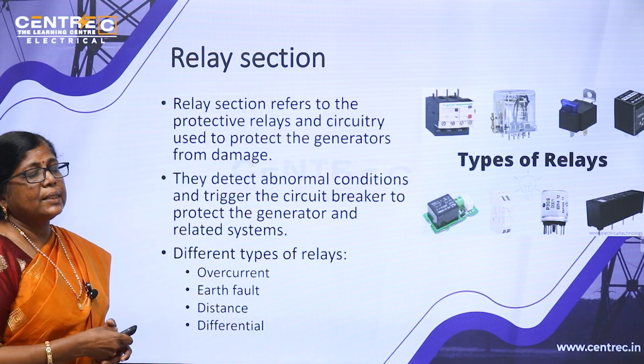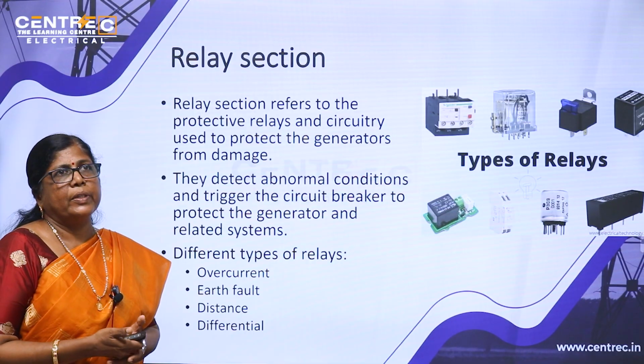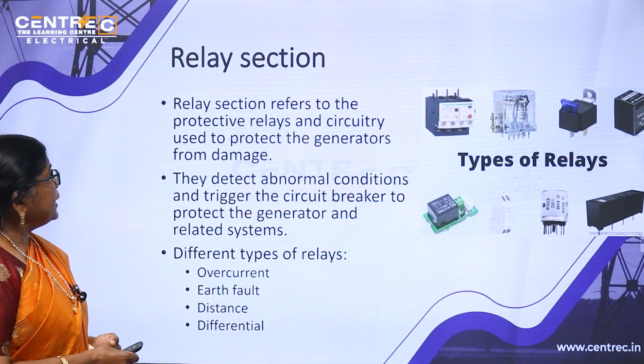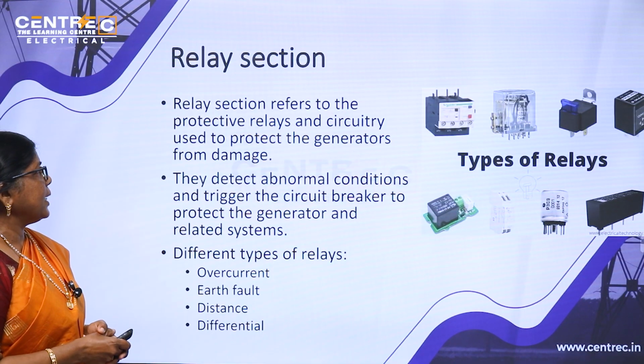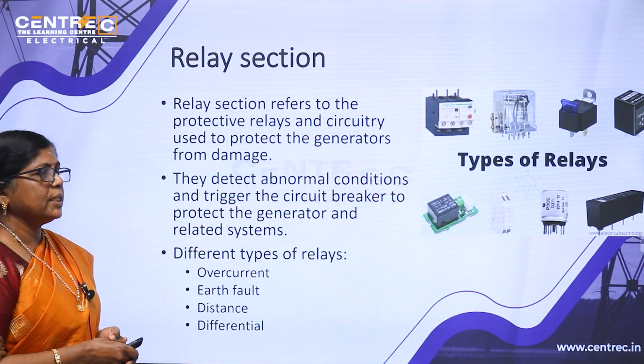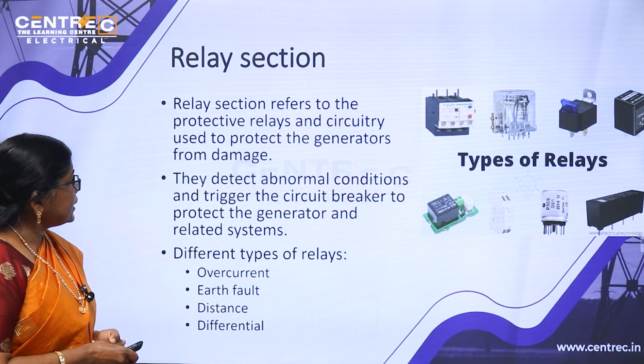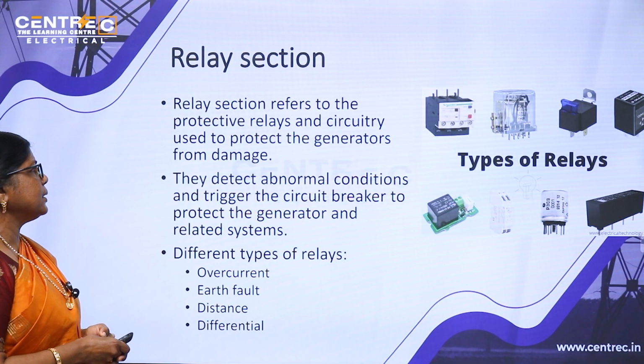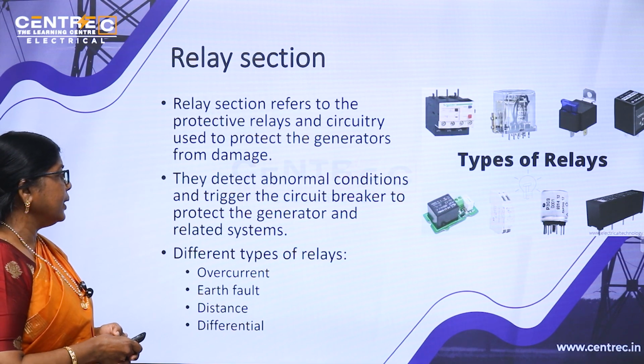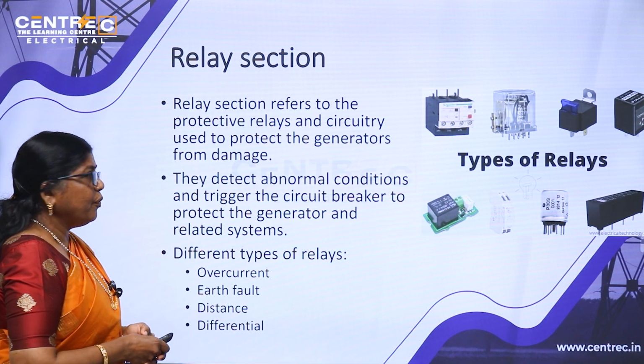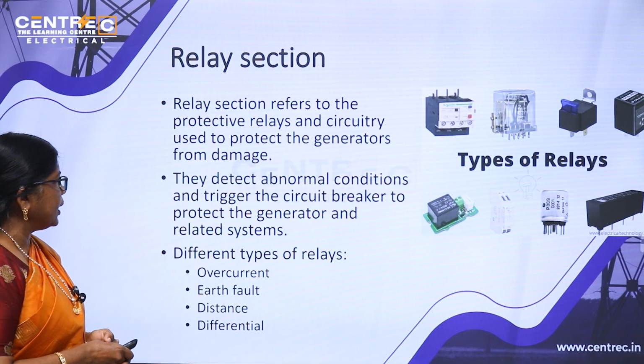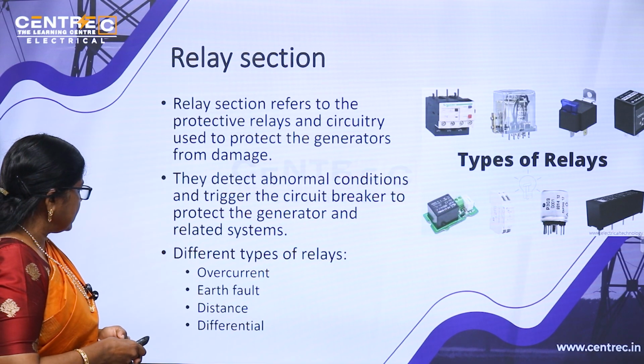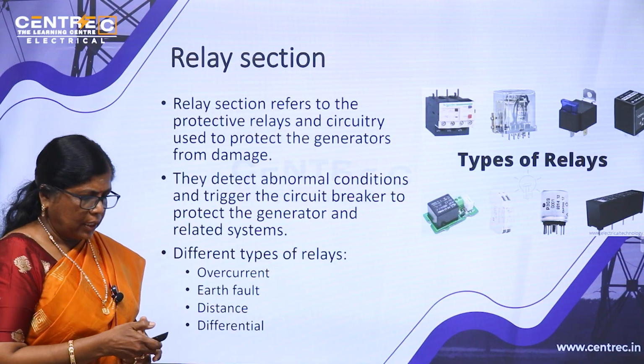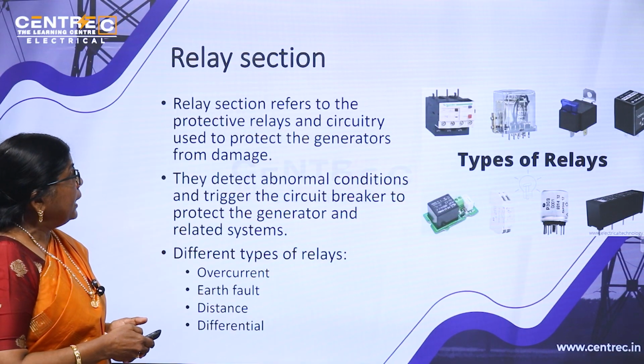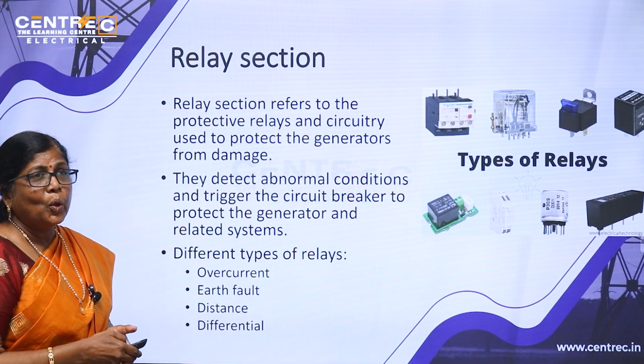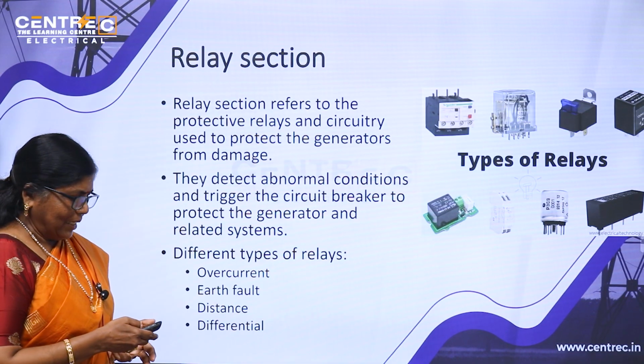Then the relay section, that is also an important section in a power station. The relay section refers to the protective relays and circuitry used to protect the generators from damage. They detect abnormal conditions and trigger the circuit breaker to protect the generator and related systems. Different types of relays are overcurrent relays, earth fault relays, distance relays and differential relays used in the stations. Mainly in a substation, we use only two, overcurrent and earth fault relays.